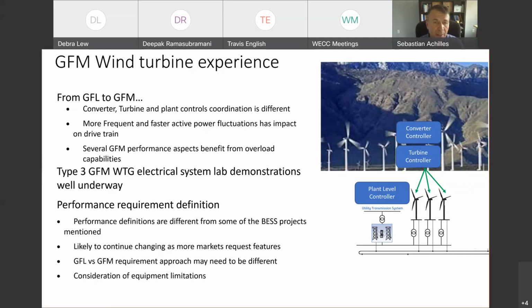There are several grid forming performance aspects that benefit from overload. For example, if you have a RoCoF event, it will be very helpful if the wind turbine can operate at higher than rated power, or similarly with reactive power aspects. The experience with the type 3 grid forming concepts we've been demonstrating is very encouraging, and it has an advantage with respect to other concepts in terms of overload. So we're well underway with this.